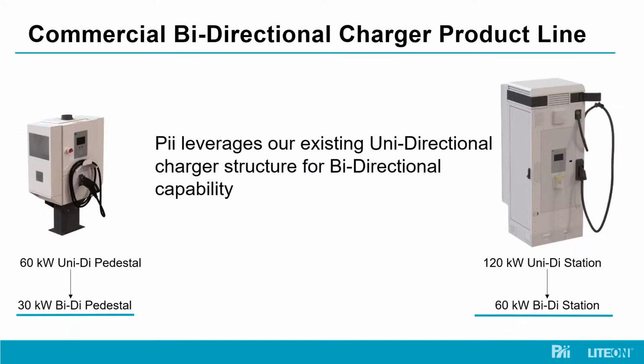So for PII's bidirectional charger product line, what we are doing is leveraging our existing unidirectional charger structure to create that bidirectional product line. So I mentioned our 30, 60, all the way up to 180 kilowatt systems, and we're able to leverage that same overall mechanical structure of what houses the power packs and take that same structure and leverage it to bidirectional. So for a 60 kilowatt unidirectional charger, for example, you may get 30 kilowatt bidirectional capability out of that. And again, it doesn't matter necessarily making sure that you have equal power. It can be 20, 40, 50, 10, whatever it may be. But all of that is possible within the 60 kilowatt unidirectional pedestal.